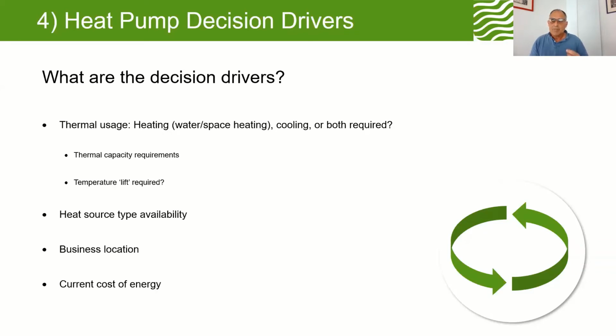Then we have to look at the temperature lift. That's the starting point of what our heat source is, to what our target temperature is, what our heat sink will end up being. And we may have different heat source availability. Because we're talking about lower inlet temperatures, which may be different from our target temperature, that could be a river, a dam, or the ground, where you can take heat out for ground source heat pumps, or a mechanical process.